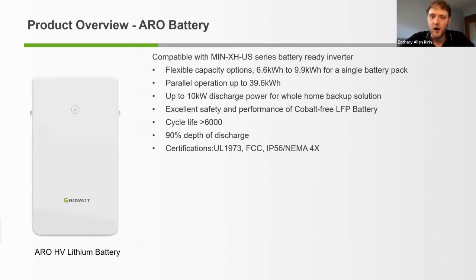So we'll start out with the ARO high voltage battery. The ARO high voltage battery is suited for the MIN US inverter. It features flexible capacity options between 6.6 kilowatt hours to 9.9 kilowatt hours for a single battery cabinet, and can be operated in parallel with multiple ARO battery cabinets to increase the capacity up to 39.6 kilowatt hours. With a single ARO battery, the discharge power is 5 kilowatts in off-grid mode, but can be expanded to discharge up to 10 kilowatts to support the customer load during those grid outages.